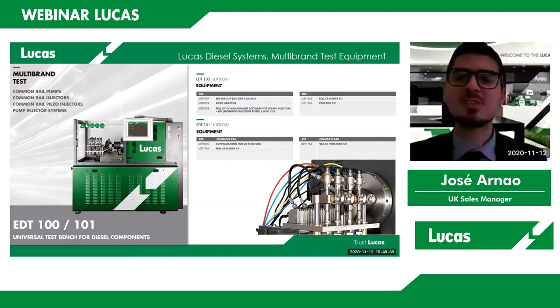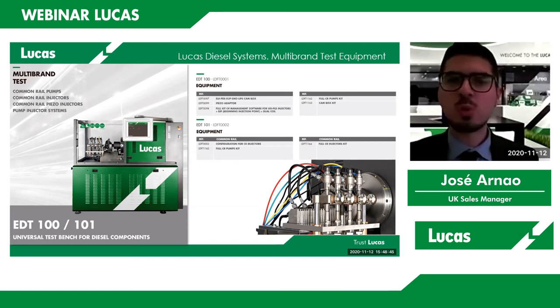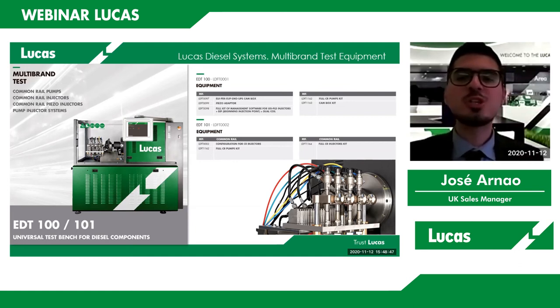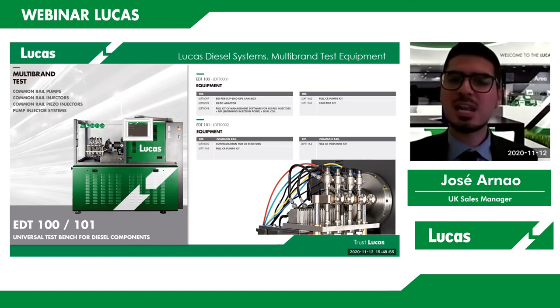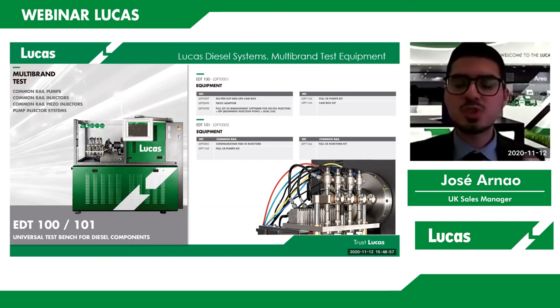This equipment is able to generate the trim codes for all brands after finishing the testing. The last feature I'd like to highlight is that we use a metering system that needs no maintenance and no calibration, because we use the Coriolis effect in the metering system.